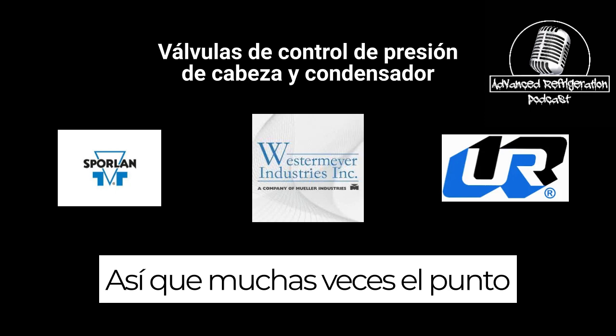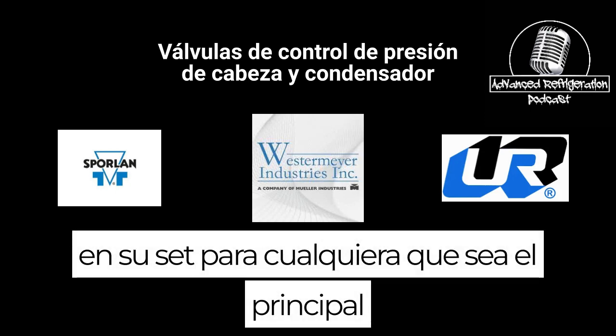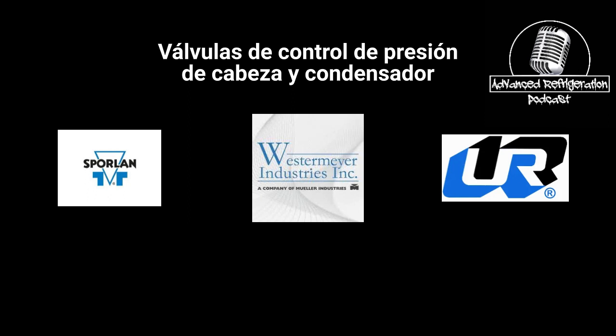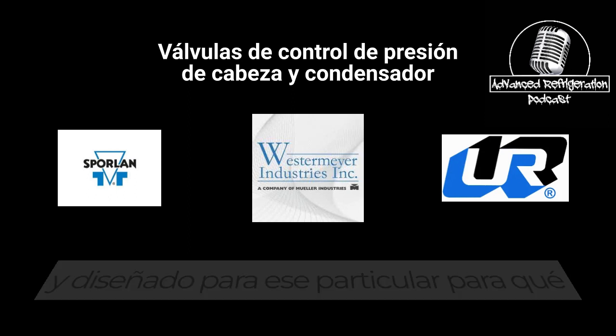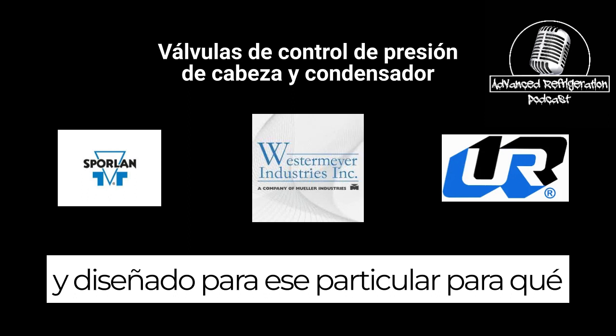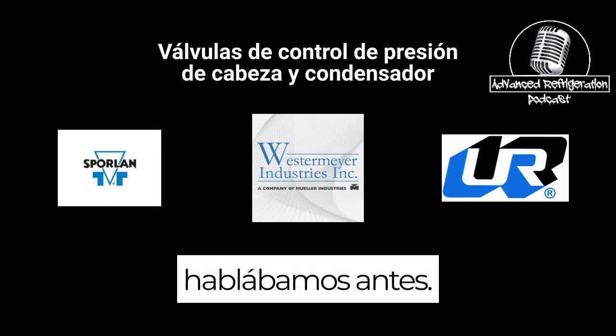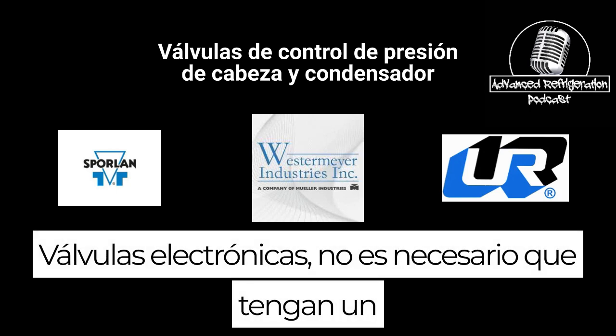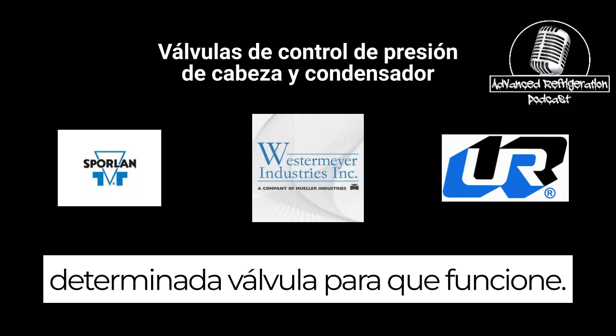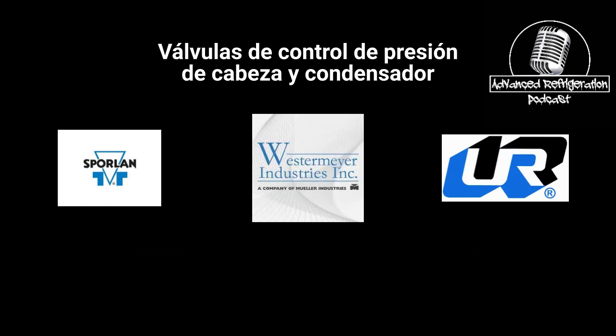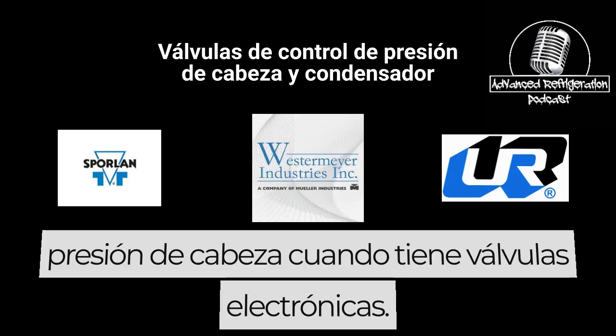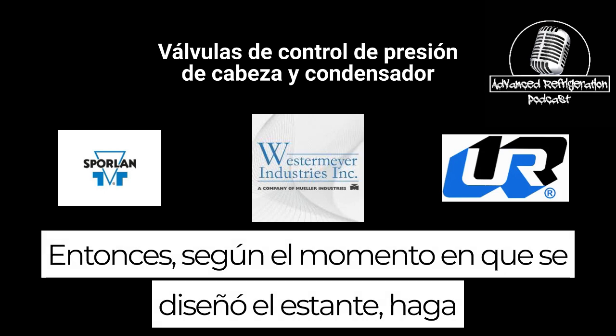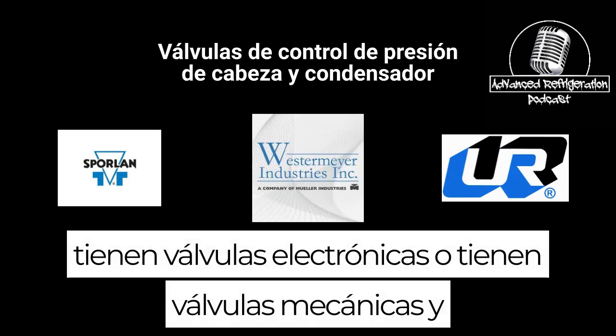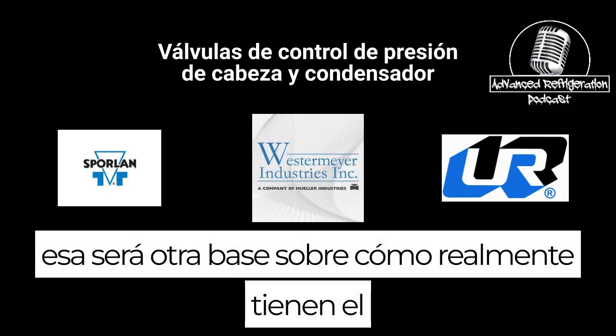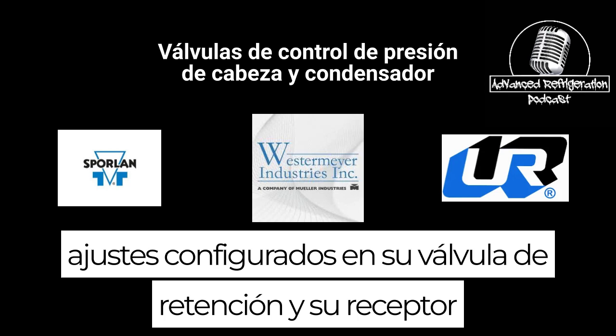A lot of times the point will be set for whatever the customer wants, whatever they're trying to maintain. You always want to go off of customer spec. They bought and had that equipment engineered and designed for that. Because what we were talking about before, with electronic expansion valves, you still have to have a certain delta across the valve in order for it to work, but they're not limited in that aspect. So you're able to run lower head pressure when you have electronic valves. So based off of when the rack was designed, did it have electronic valves or mechanical? That'll be another basis for how they have the settings set up on their holdback valve and their receiver pressurization valve.